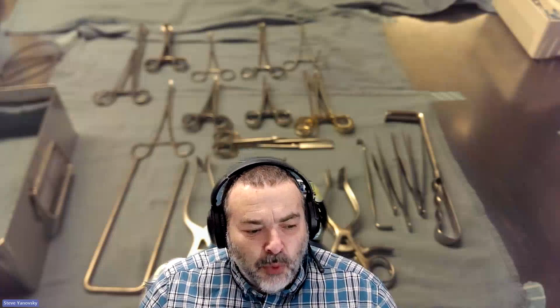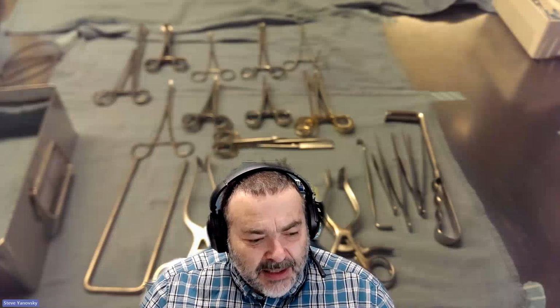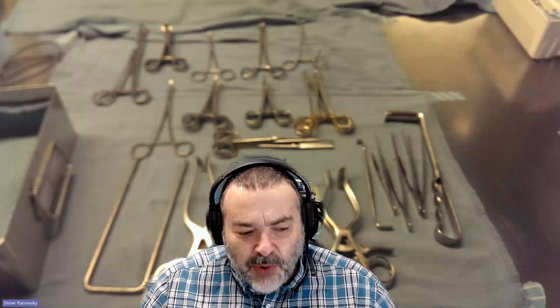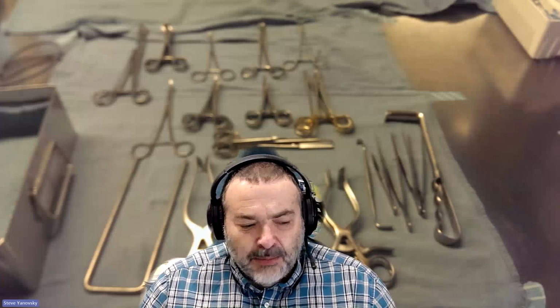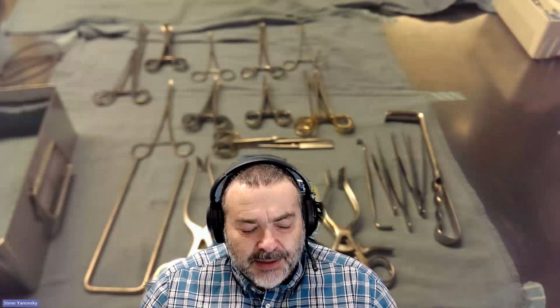Well, the most important function, which is done daily, is to clean the drain. The other one is to check and clean the door gasket. But it's the drain that must be cleaned. And if you don't clean the drain, it's the most common cause of wet packs. Wet packs are caused by improper or inability of the machine to evacuate steam or air for that matter. So if the drain is clogged, you got problems.